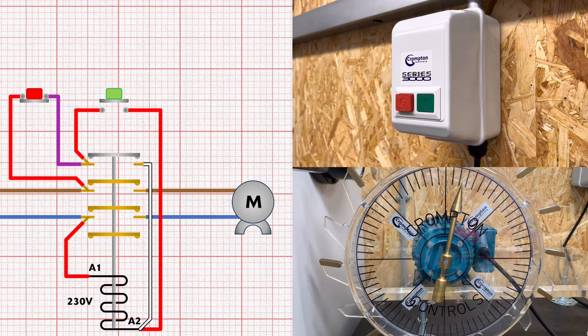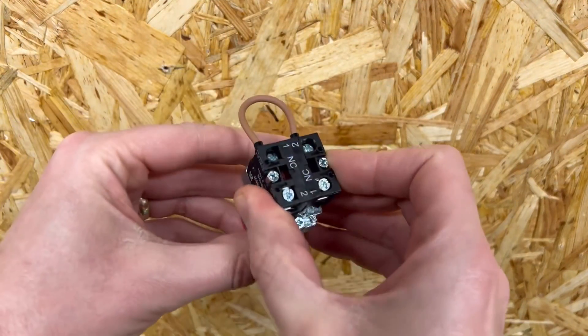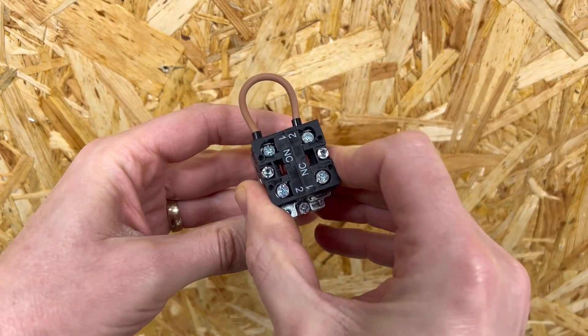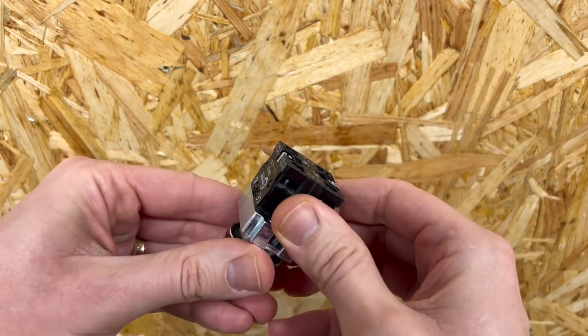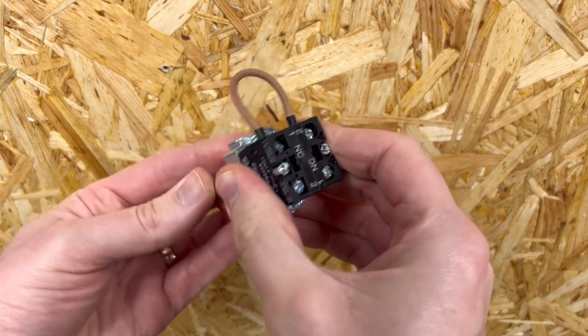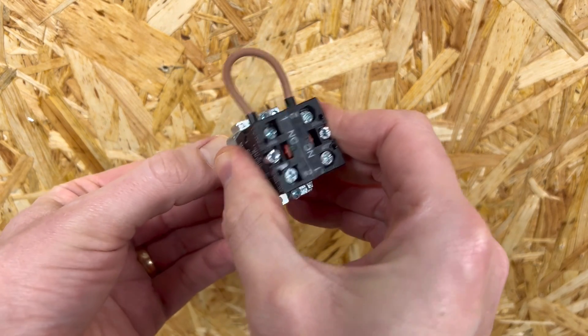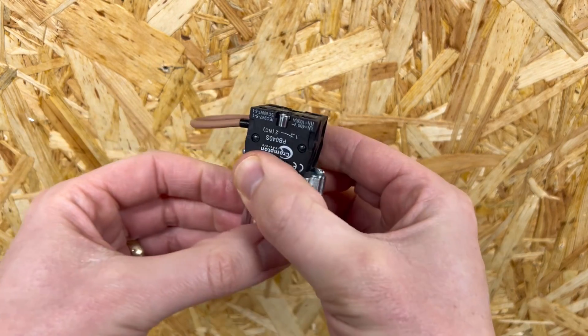Because the auxiliary contact is disconnected, the motor won't start again until the start button is pressed. You may sometimes come across stop buttons with two normally closed contacts wired in series with each other. This is an added safety feature because sometimes the contacts can become jammed or slightly welded together, meaning they won't open when pressed. Having two contacts wired in series means you've got a backup in case one of the contacts doesn't operate.